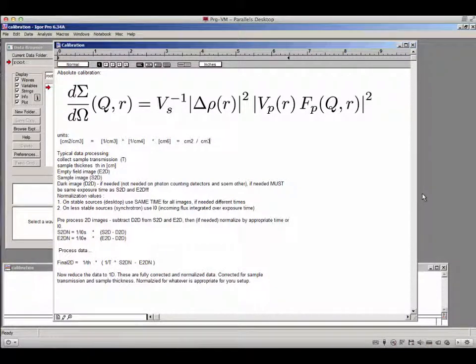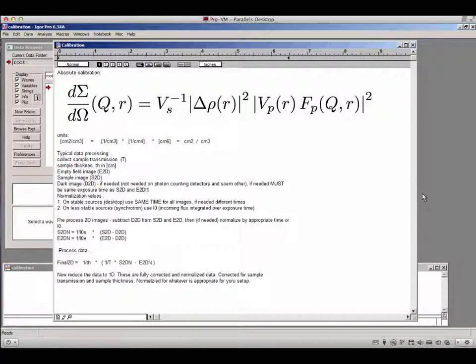Welcome. This movie will explain how to do absolute calibration using a secondary standard, most likely a glassy carbon standard — a piece of about 10 to 15 by 15 millimeters, one millimeter thick, provided by me or possibly bought from NIST, which is absolutely calibrated using our USAXS instrument at the Advanced Photon Source.